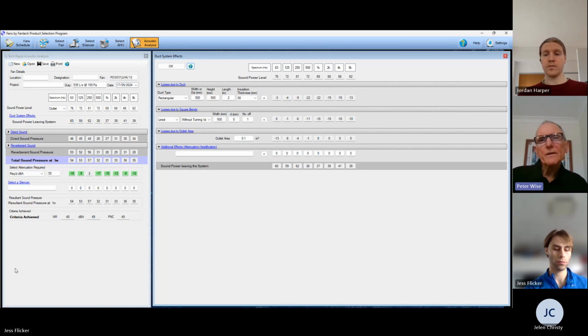So all we did - we had the exhaust ducts run horizontally and then vertically, and the fan was just above the roof. All we did was put internal insulation in the vertical riser, so that the sound coming in the horizontal parts and then up towards the fan got attenuation where we could get it in the vertical riser of the duct. It was only about, say, 2 meters long, and that brought the sound down a lot. So that's all we needed to do, and we did that quite easily. I mean, we should have done it in the first place, but the decision was made not to worry about it, and it was an issue.